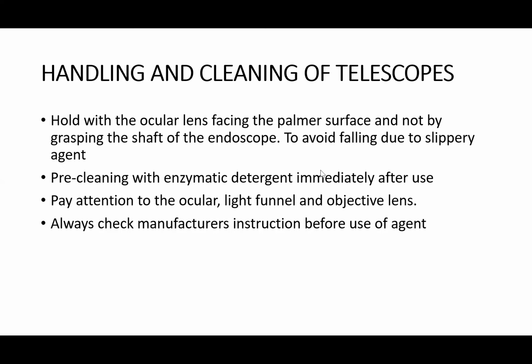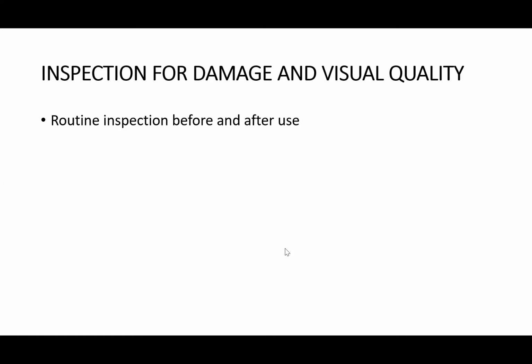Okay, and you have to pay attention. We describe the telescope as having the ocular lens, the objective lens, and the light funnel through which the light source is transmitted. So you have to pay attention to these parts to clean properly. And you have to ensure you are using agents that are recommended by the manufacturer, because if you use agents that will cause cracking or blurring of the lens, you may have very poor vision. Or agents that may cause clouding of the lens may affect the vision of your instrument.